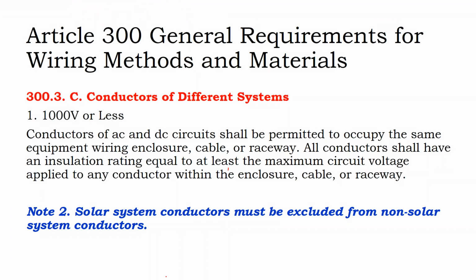Conductors of AC and DC circuits are permitted to occupy the same equipment or enclosures. All conductors shall have an insulation rating equal to the maximum circuit voltage of any conductor within the same enclosure and raceway. And so you're allowed to have AC circuits and DC circuits in the same enclosure, but you have to check your voltage requirements. Remember that DC or AC services are common at 240 volts, 120 volts, maybe 480 volts. And that might mean the jacket of that cable is not rated for the same 600 volt rating that solar could go all the way up to. So you've got to check your jacket rating voltage requirements when you're sharing the same thing.